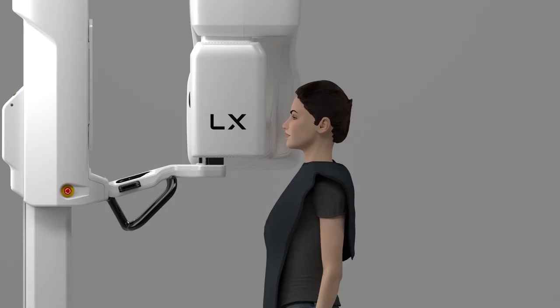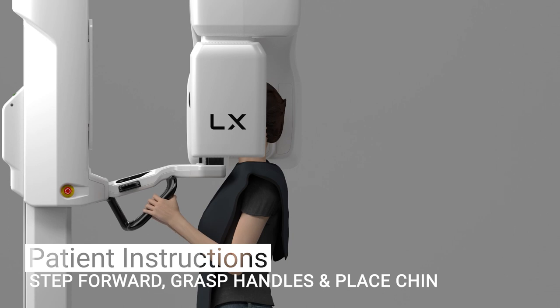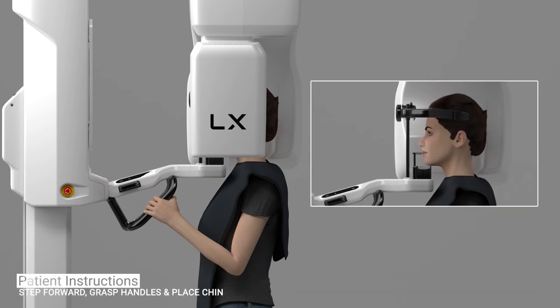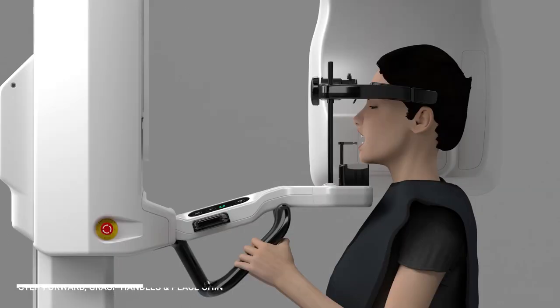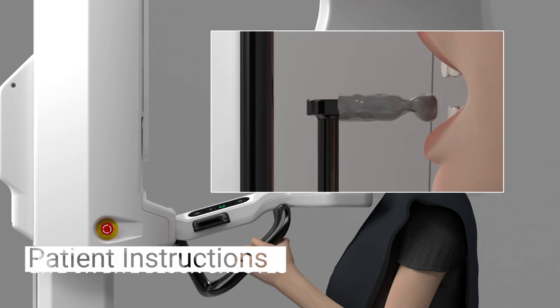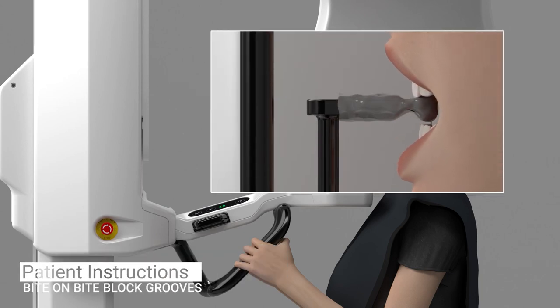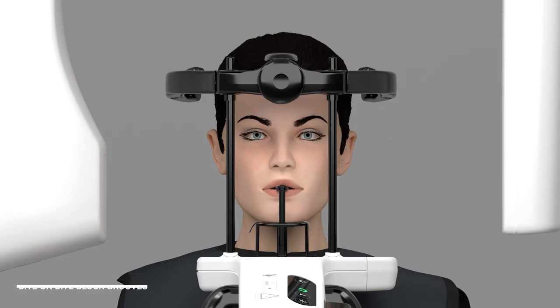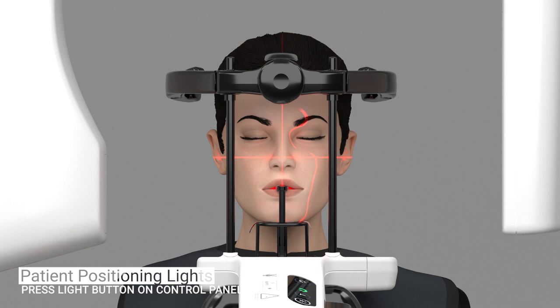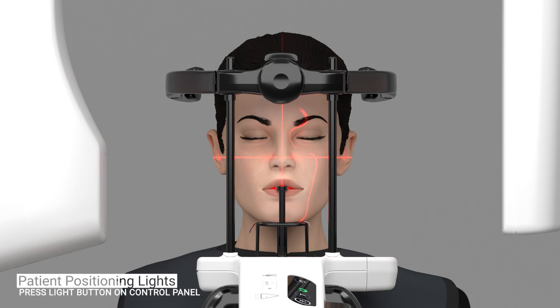Have the patient step forward, asking them to grasp the patient handles, place their chin onto the chin rest, and bite on the bite block so that both their upper and lower anterior teeth are in the bite block's grooves. Tell the patient to close their eyes, turn on the patient positioning lights by pressing the positioning light button on the control panel. Adjust the device's height and adjust the patient's head position using the patient positioning lights as guides.